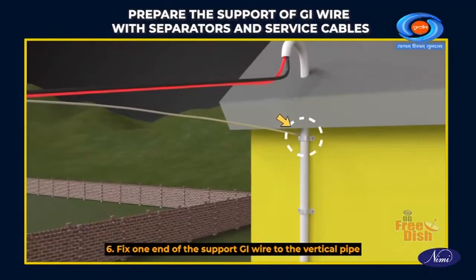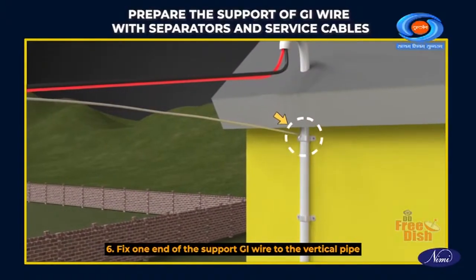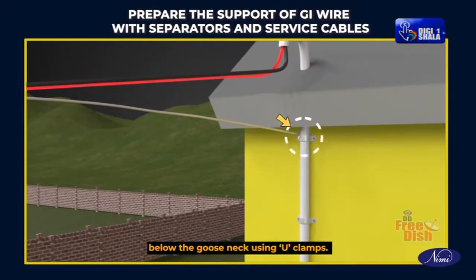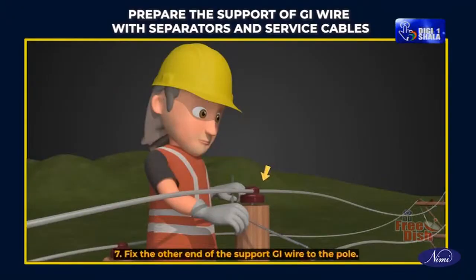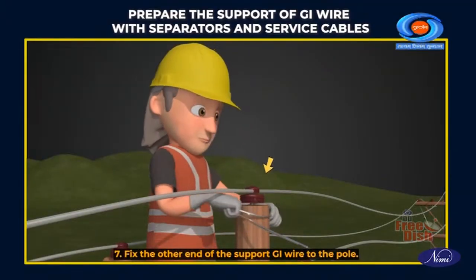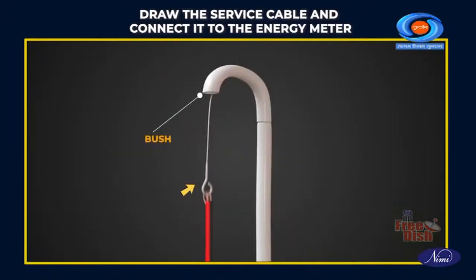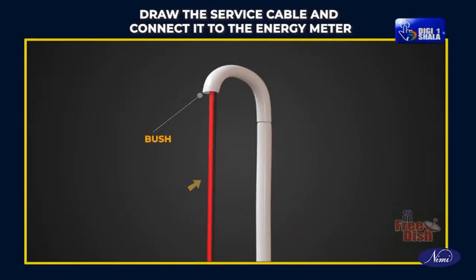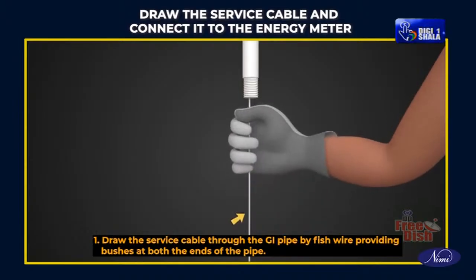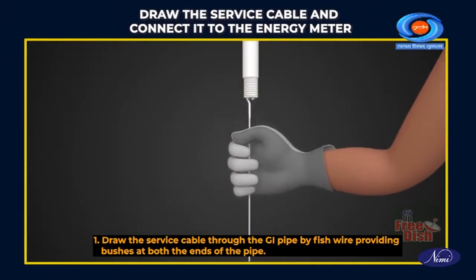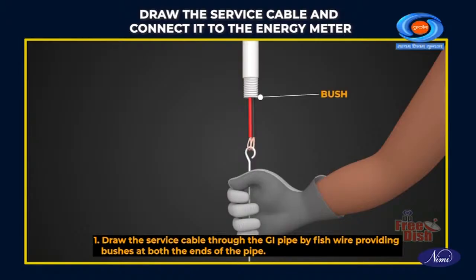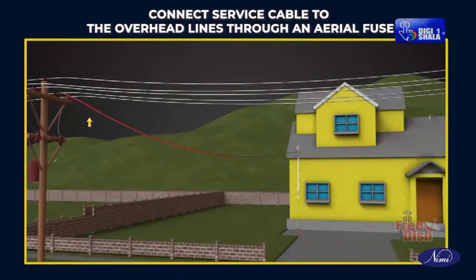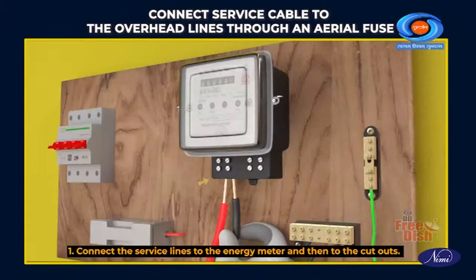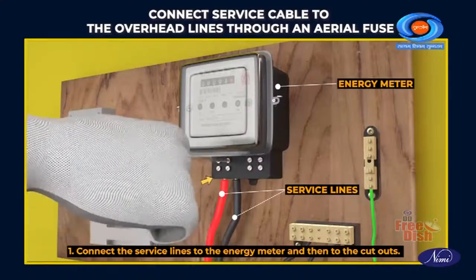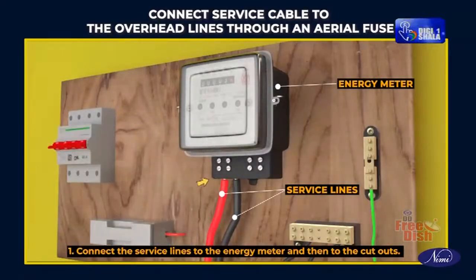Fix one end of the support GI wire to the vertical pipe below the gooseneck using U clamps. Fix the other end of the support GI wire to the pole. Draw the service cable and connect it to the energy meter. Draw the service cable through the GI pipe by fish wire, providing bushes at both the ends of the pipe. Connect service cable to the overhead lines through an aerial fuse. Connect the service lines to the energy meter and then to the cutouts.